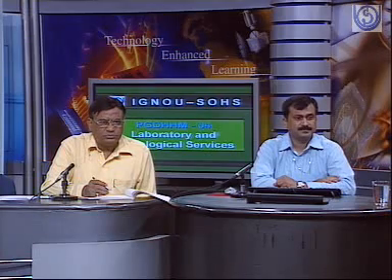Generally, we are talking about the hospital security and safety, and most of the centers that have come up in the market are only imaging centers. And there, all the safety norms are not being taken care of. Actually, I can answer your question by going into AERB guidelines. For any X-ray machine which needs to be installed, there has to be an AERB clearance, and that has to be meticulously followed. Unless the drawings and design are passed by AERB, they cannot operate a center.